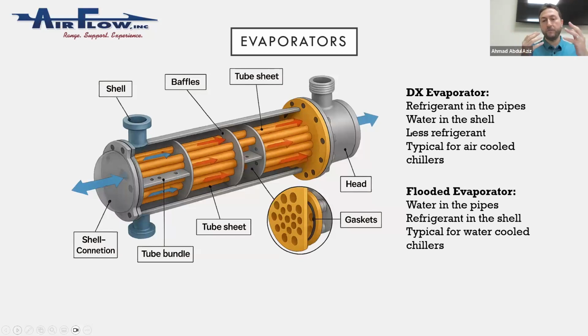Now, both of them have pros and cons, but again, as a chiller buyer, you look for the output of the chiller as a system. You are not looking at each item inside, like what about your condenser, what about your evaporator. You are not buying items. You are buying one full system. So the main difference: with DX, you have less refrigerant inside your system. With flooded, you have a larger amount of refrigerant inside your system.